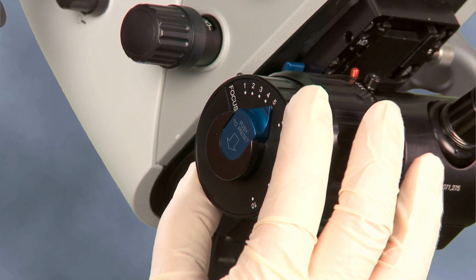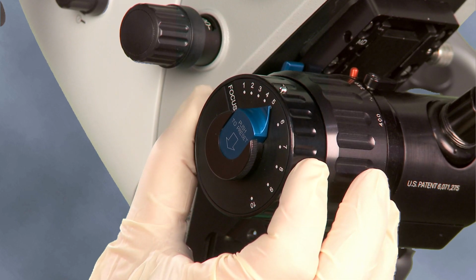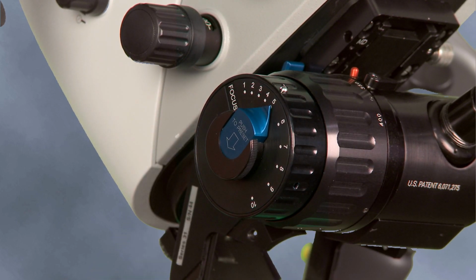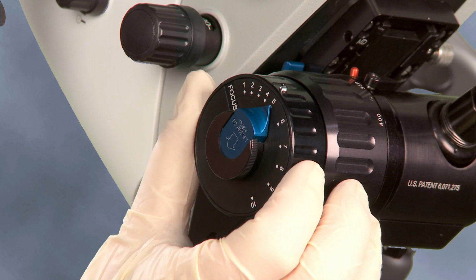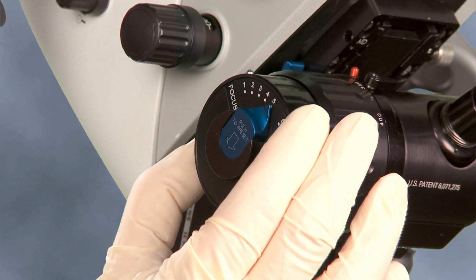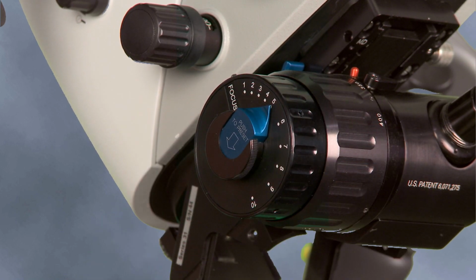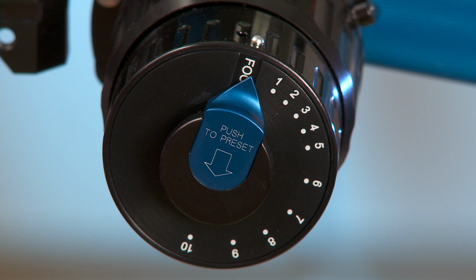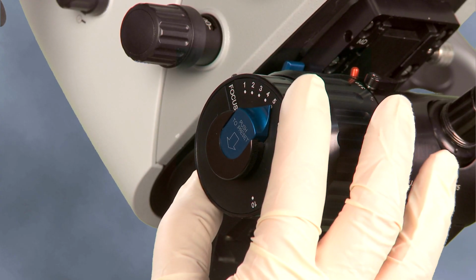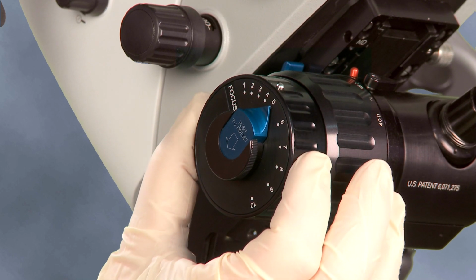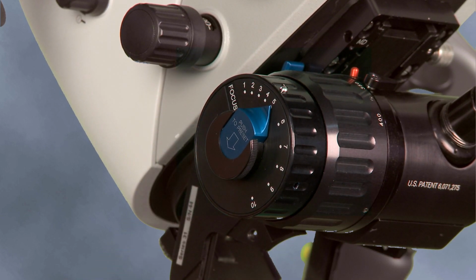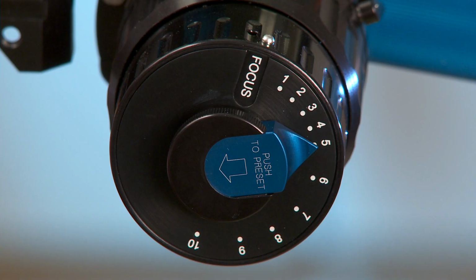The spot size selection knob has 11 settings, focus and defocus 1 through 10. When the system is parfocal and the spot size knob is set to focus, the diameter of the laser beam on the tissue plane will be smallest. To enlarge the beam spot, simply rotate the knob. The spot diameter is largest at 10.